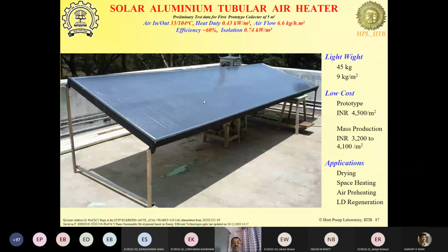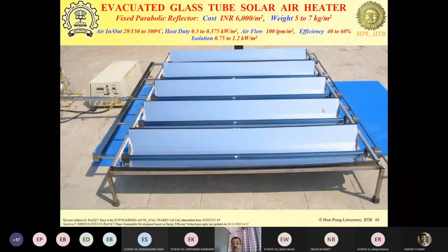In this air heater, we could heat up the air up to 119.6 degrees centigrade from around 33 degrees centigrade. Okay, this particular data is for 104 degrees, 33 to 104 in one. So the 33 degree air enters here and the 104 degree air comes out from here. Just in less than 2 feet travel, we are able to heat it up. And the weight is also very less. These are the air heaters for high temperature.